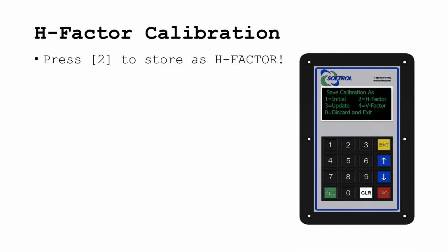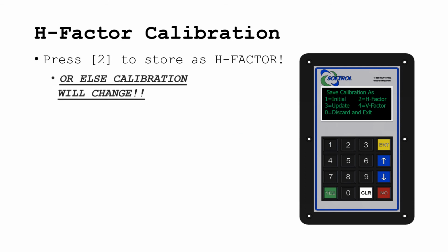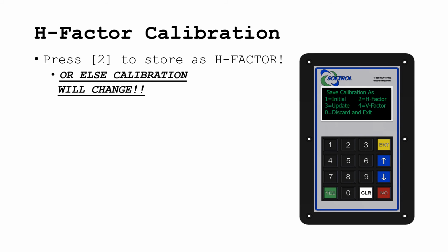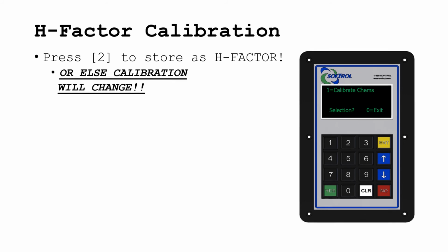Now, you press the 2 key to store the calibration as an H-factor calibration. This is very important or else the calibration will change and be overwritten. After, the display will return to the calibration menu.